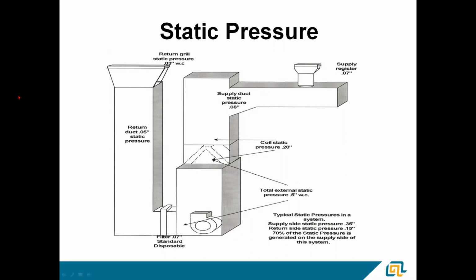70% of the static pressure is going to be generated on the supply side. So if those two numbers were reversed, if you had a return side static of 0.35 and a supply of 0.15, there's definitely an issue in that return. So higher static pressure number on the supply side, lower on the return, which only makes sense. When we're supplying that air, we're pushing that air, it's going to have a lot more pressure against it than as it comes down that return duct.